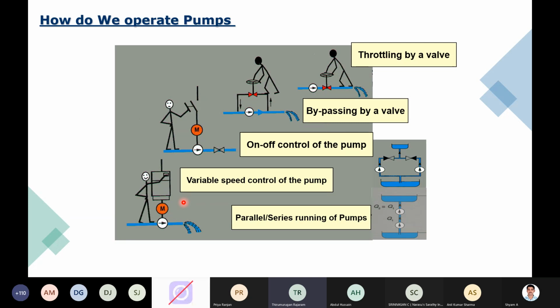Now you can find large pumps also being adapted for variable frequency drive operation. That makes sense because your energy saving would be high, since any plant is not going to operate at full load. If you talk about the current pandemic, how many industries were running full load? Very few. Maybe pharma was one industry running 24/7, but many industries were running at very lean load, 10% to even 50% load scenarios. With a variable speed drive, your demand can be accurately met for that lean demand, your energy cost will not be very high, and your profits are protected.